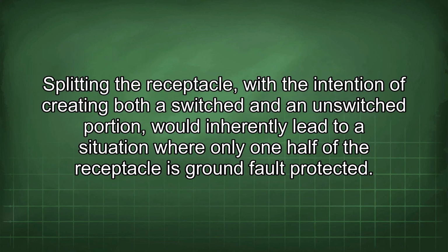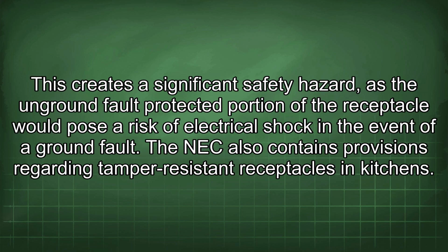Splitting the receptacle with the intention of creating both a switched and an unswitched portion would inherently lead to a situation where only one half of the receptacle is ground fault protected. This creates a significant safety hazard, as the unground fault protected portion of the receptacle would pose a risk of electrical shock in the event of a ground fault.